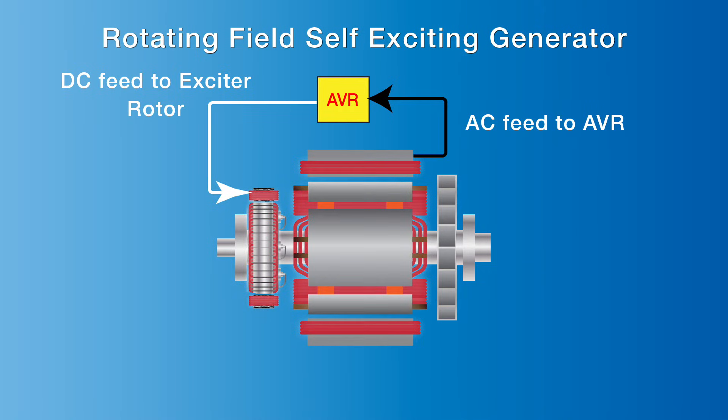If the AVR's reference voltage falls, it increases DC current to the exciter coils and reduces this current if the reference AC voltage is too high.